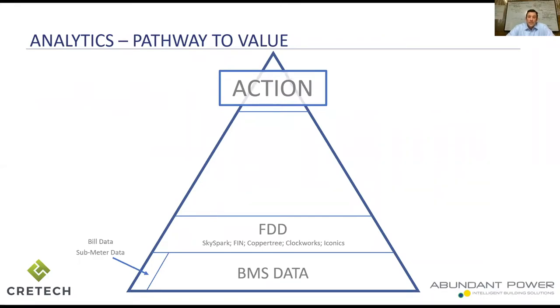The reality of where analytics is today is that somebody has to look at these faults and come up with a recommended action — we call that curation. I could pull up a Class A office tower right now and see over a thousand faults over the last few weeks — that's way too much information to take action with. Someone has to go through those, prioritize them, and come up with an action. We've put a lot of effort into post-processing tools — making it easier for a mechanical engineer, certified energy manager, or someone strategic to curate what really matters for their buildings. We're starting to feather in proper artificial intelligence and machine learning to help the curation process even further.